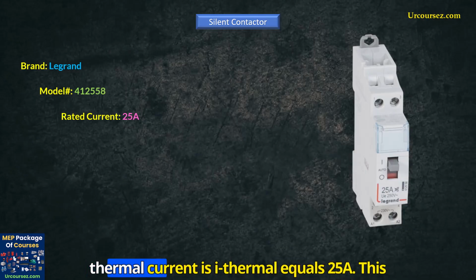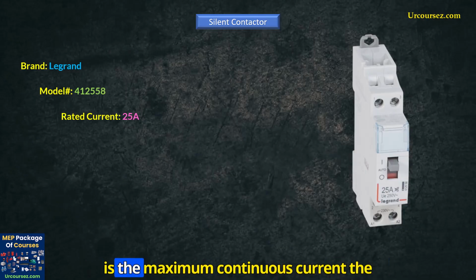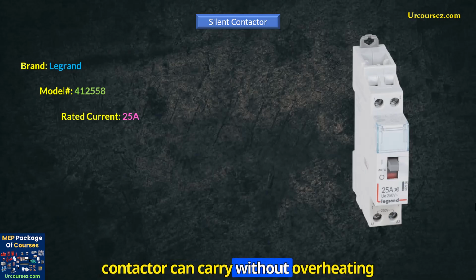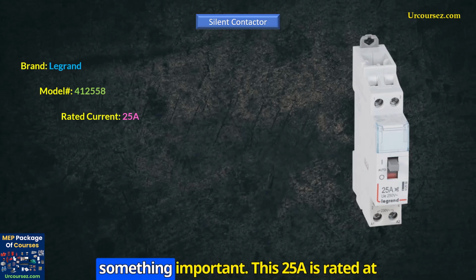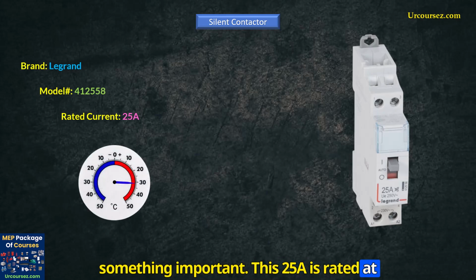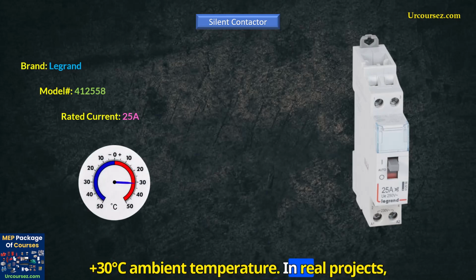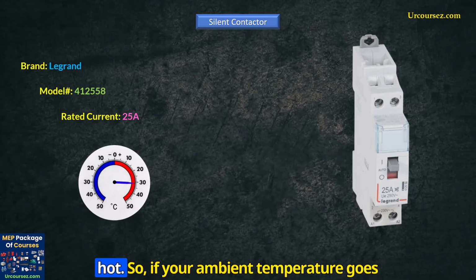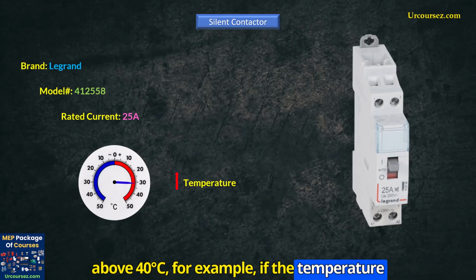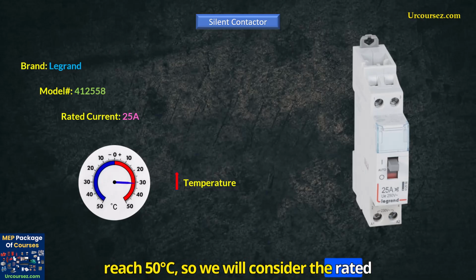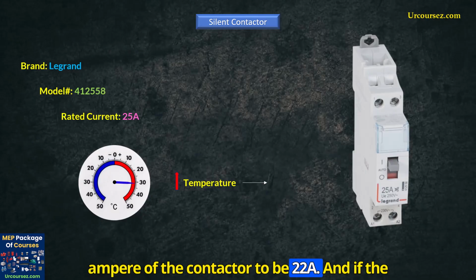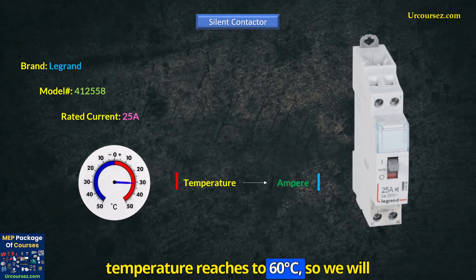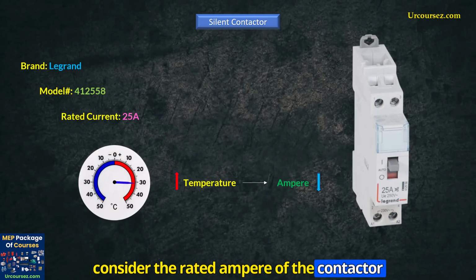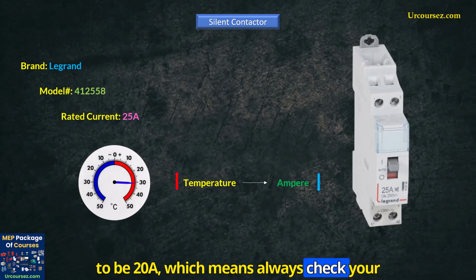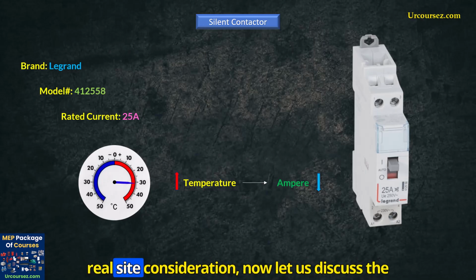The conventional thermal current is I thermal equals 25 amperes. This is the maximum continuous current the contactor can carry without overheating under normal conditions. But here's something important. This 25 ampere is rated at plus 30 degrees Celsius ambient temperature. In real projects, especially in the Middle East, panels can get hot. So if your ambient temperature goes above 40 degrees Celsius, for example, if the temperature reaches 50 degrees Celsius, we will consider the rated ampere of the contactor to be 22 amperes. And if the temperature reaches 60 degrees Celsius, we will consider the rated ampere of the contactor to be 20 amperes. Which means always check your panel installation environment, as this is a real site consideration.